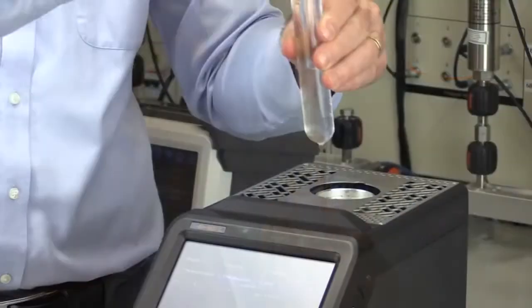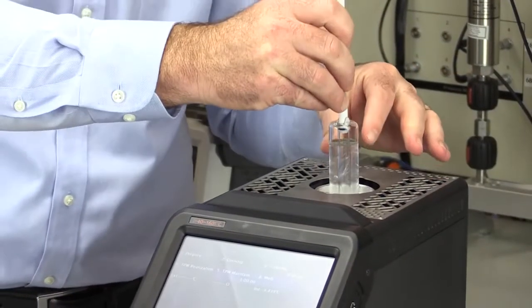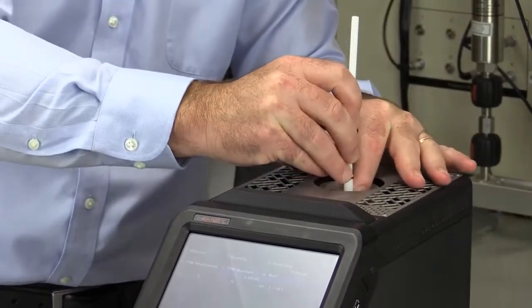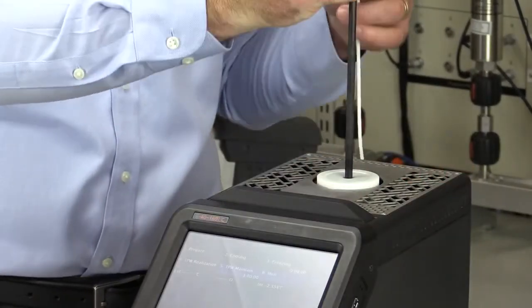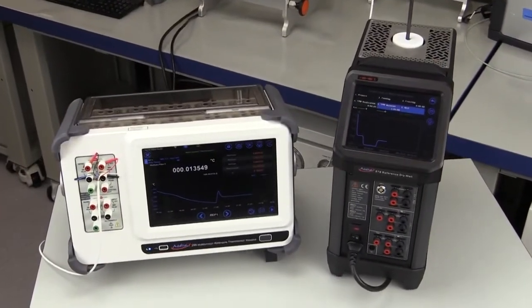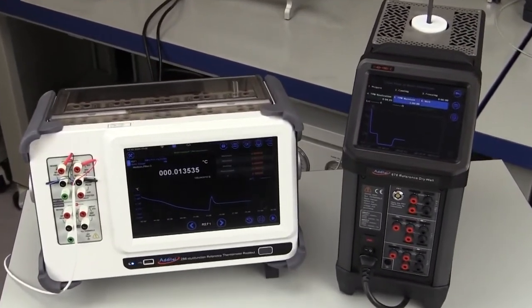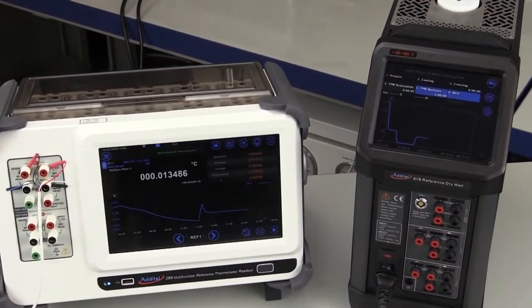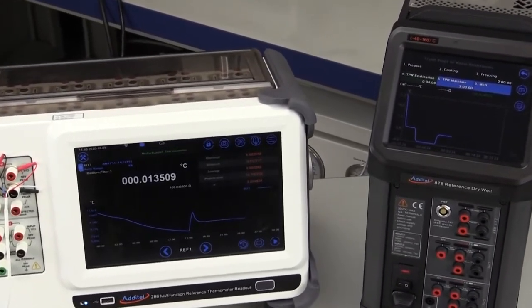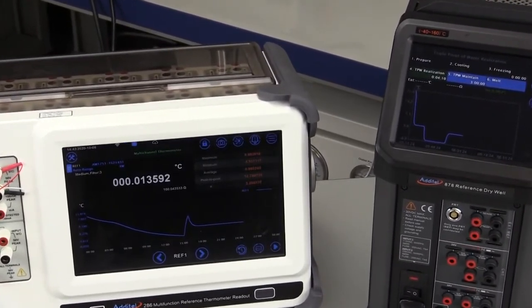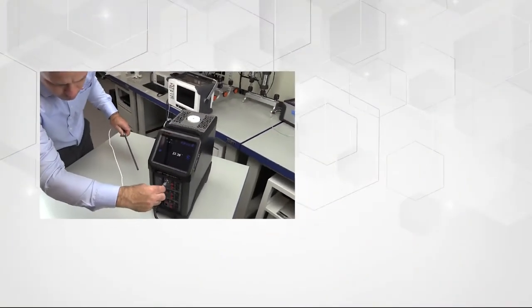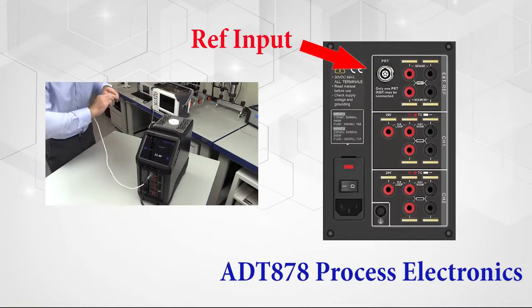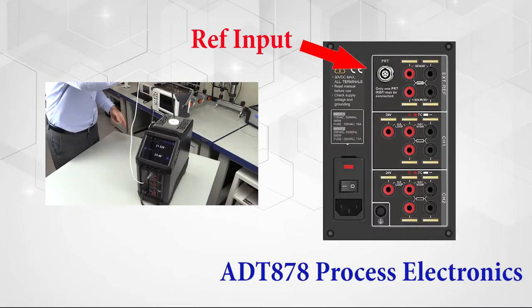Then the TPW cell goes back into the ADT878 where it can be maintained for up to 3 hours. The reference thermometer is then gently reinserted into the cell. It's a good idea to wait about 10 minutes for the system to completely stabilize. At this point, we can begin taking measurements of the reference thermometer at the intrinsic constant temperature of 0.01 degrees C.